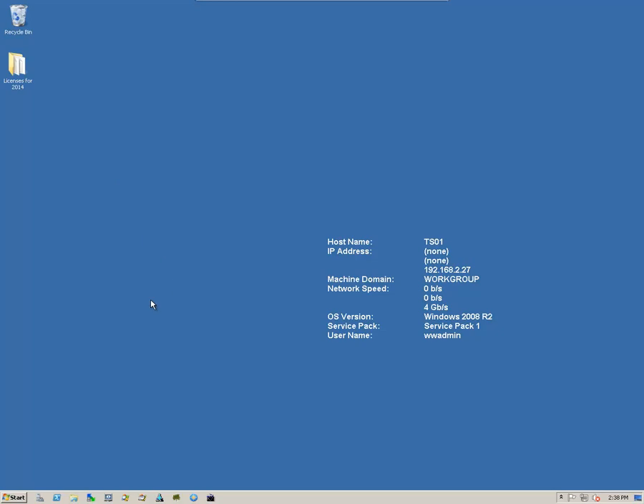So this right here concludes this video on how to validate whether your upgrade was successful. By verifying that you have data collection coming into your galaxy, data storage going into your historian, and also visualization by opening up the information server and verifying that the interface comes online. And also that you can connect to your historian and view trending information. And also verifying that your application, your InTouch HMI application correctly converts up to the current version of InTouch, which is 11.0. That is a part of the System Platform 2014 release. Thank you for watching.